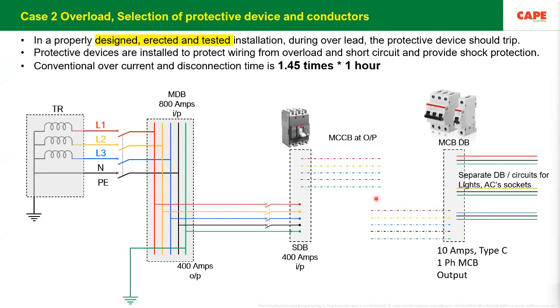So we have a lot of protective devices in our network. Nowadays we have MCCBs, MCBs and all, but in olden days we had fuses. Of course, fuses are also equally effective if they are appropriately selected and installed. Very important: if we put in an overrated device, of course, it may not work. If we put in an underrated device, then it may trip unnecessarily.